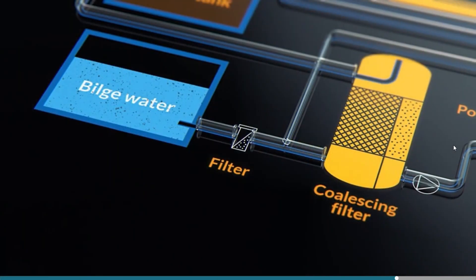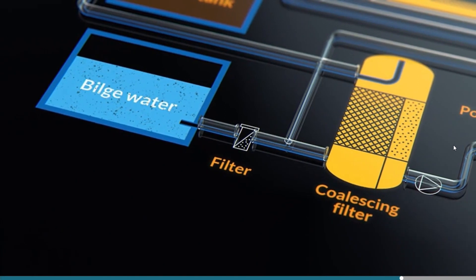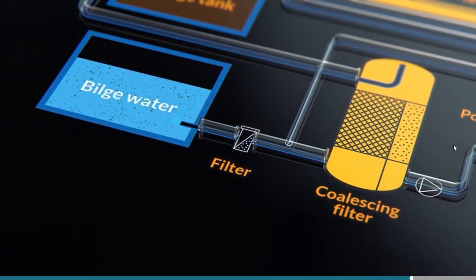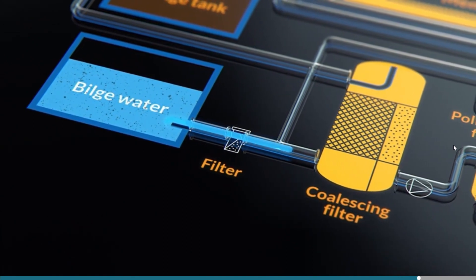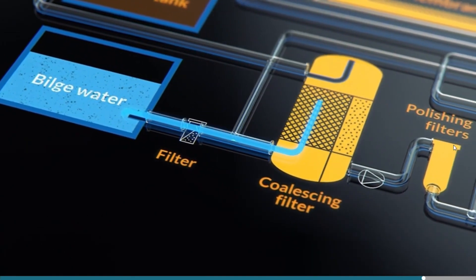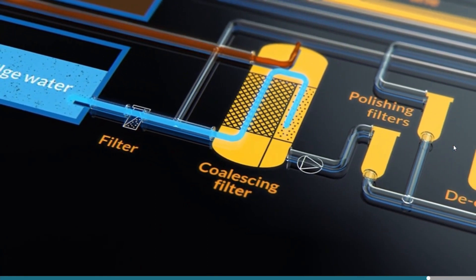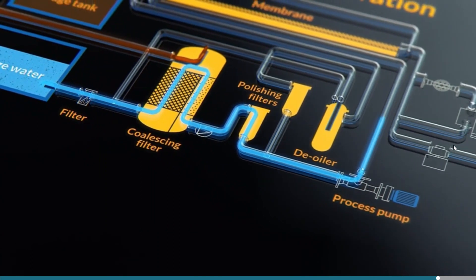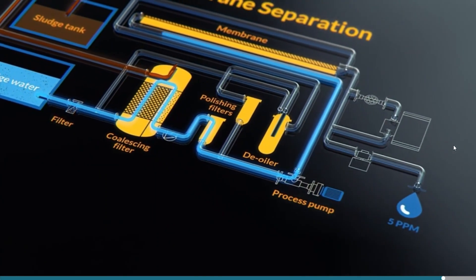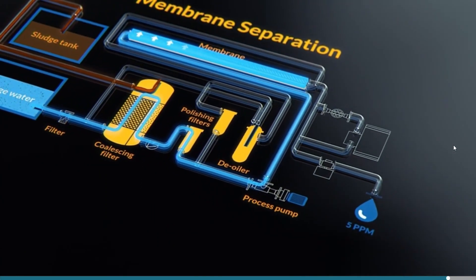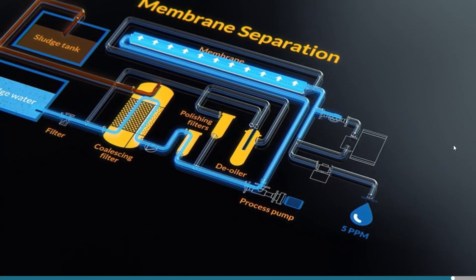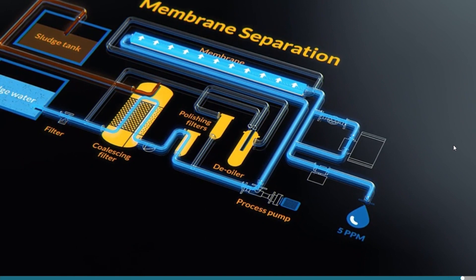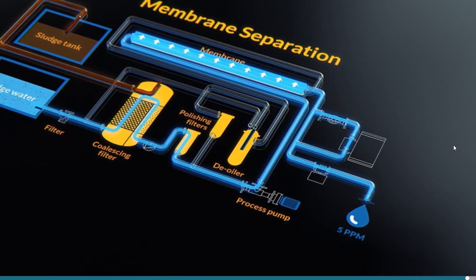The separation process in a membrane-type bilge separator takes the following steps. Step 1: In the first stage, the bilge water passes through a coalescing filter, where small oil droplets stick to the coalescing mesh. Step 2: Filtration through polishing filters, including membranes that do not allow the passage of oil droplets. Clean water then passes through the oil monitoring equipment and goes overboard.